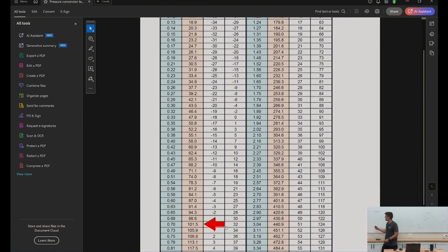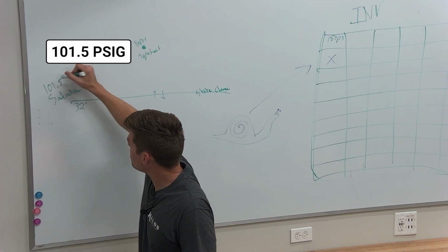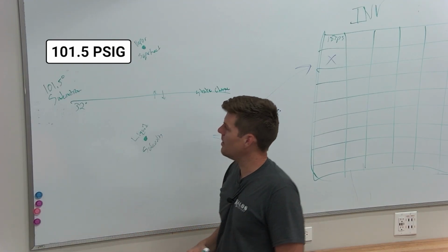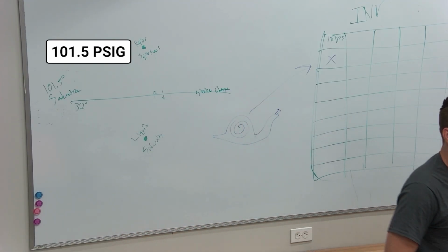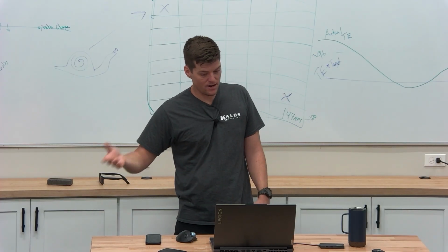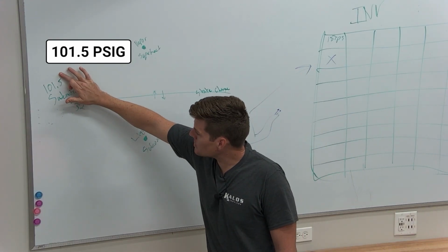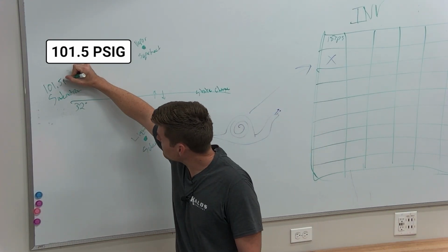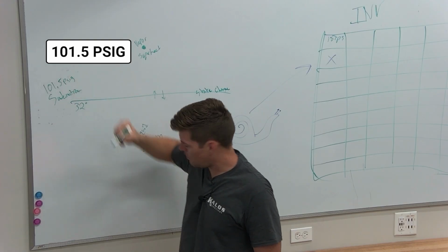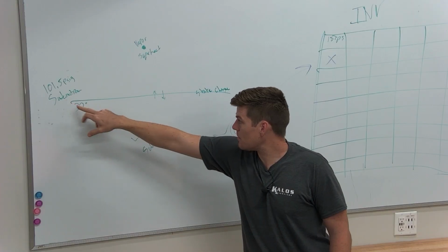101.5. You're going to notice in VRF we stopped talking about pressures because there's just too many temperatures to talk about. And let's be honest, it doesn't really matter. The system converts all of these things for us with our TE, right? So this is 101.5 pressure, not degrees, sorry. PSIG, or PSI. 32 degrees at 101 PSI, okay, right?